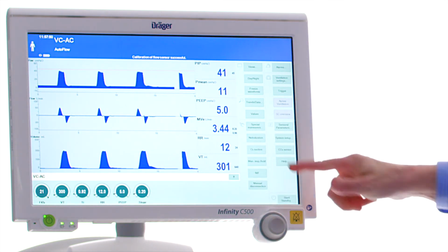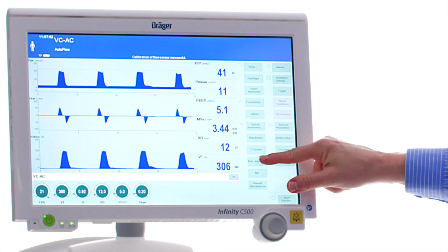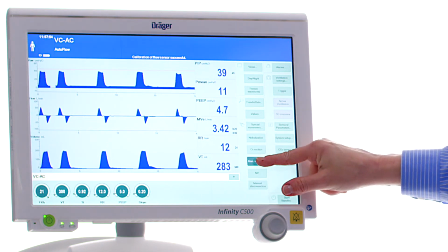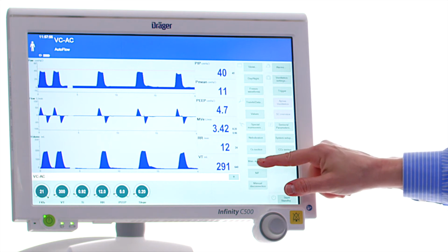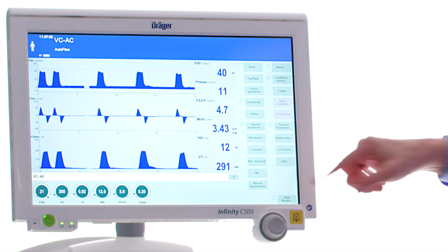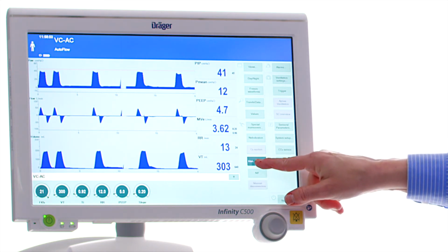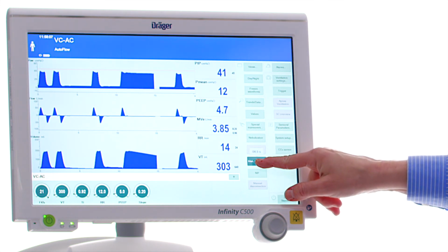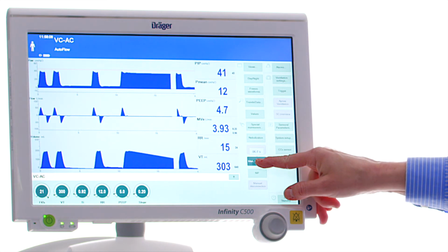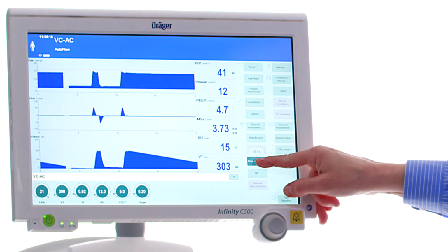In order to get a manual breath delivered to your patient, all you do is touch the manual inspiration/hold, which delivers a breath at the set parameters. It will also provide a sustained inflation by pressing and holding the button. Above your finger, you will see a timer that tells you for how long the button has been sustained, and it will continue for up to 40 seconds.